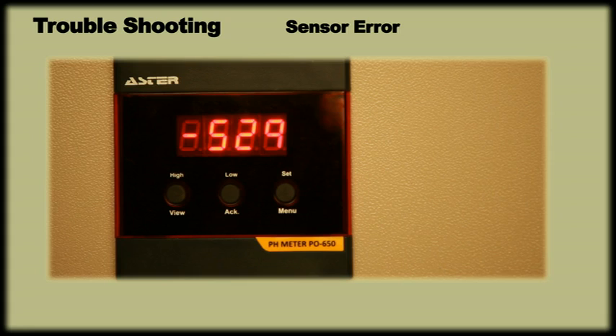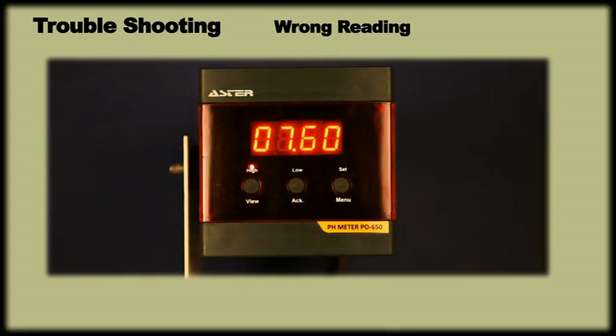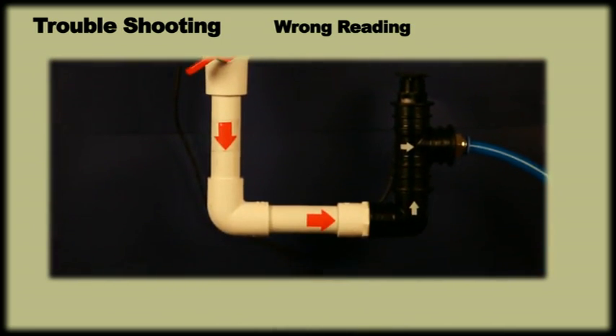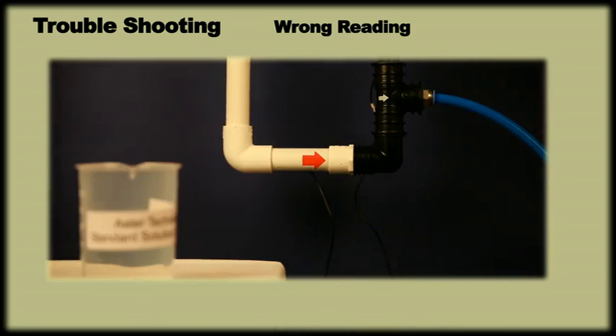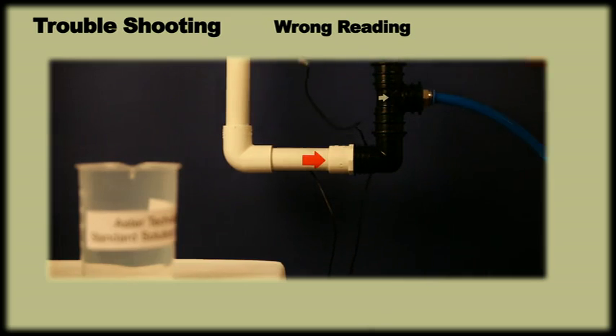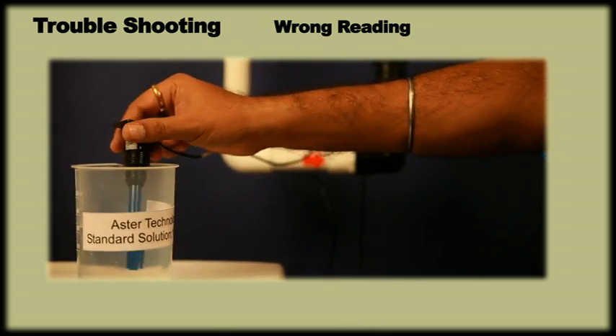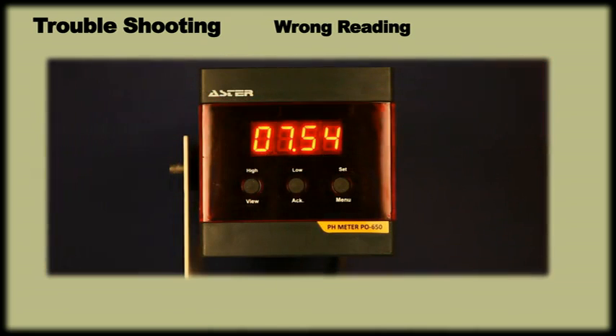If the meter shows wrong reading, it could be because of the following reasons. If the sensor is installed correctly, yet it shows wrong reading, then remove the sensor from line and test the sensor in standard solution of 7 and 4 pH. If it still shows wrong reading, then recalibrate the meter. The wrong reading could also be due to very low conductivity in the water. Contact service center.